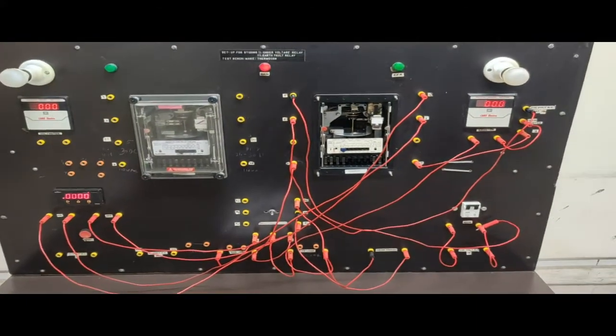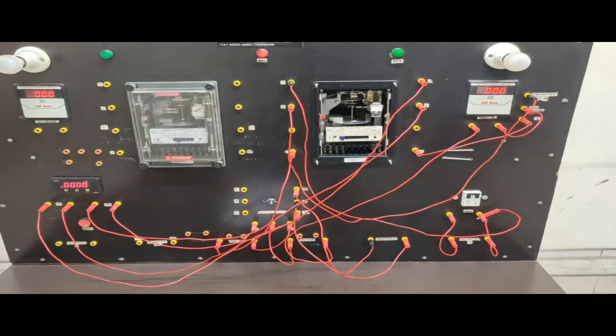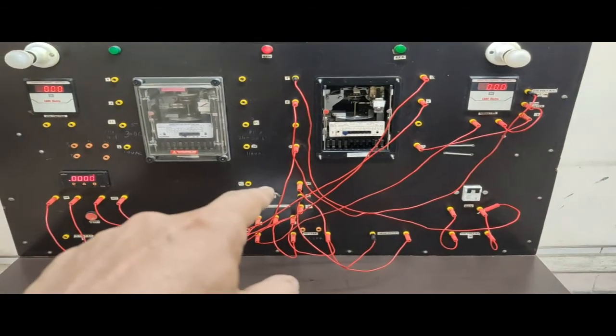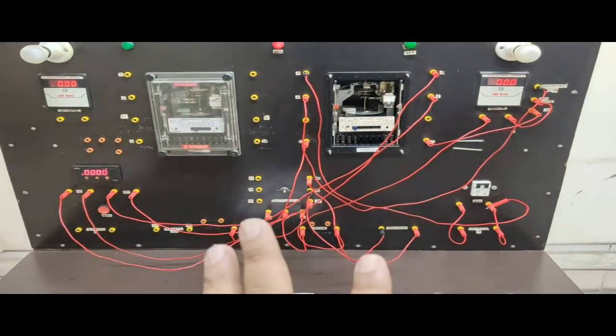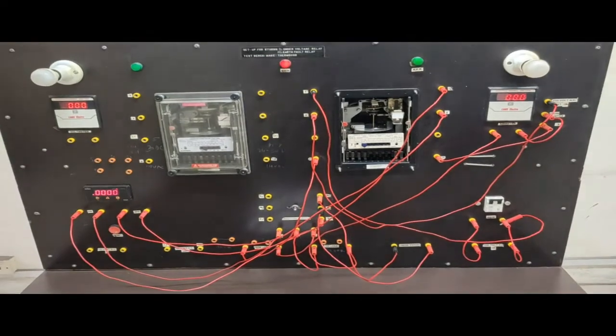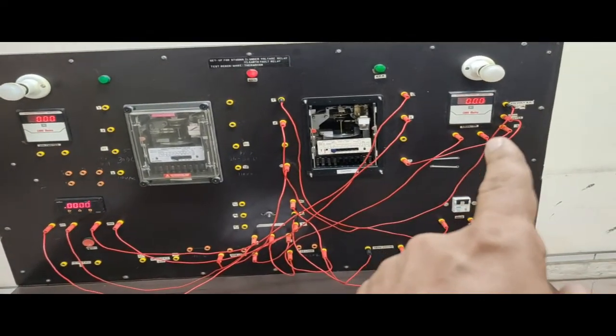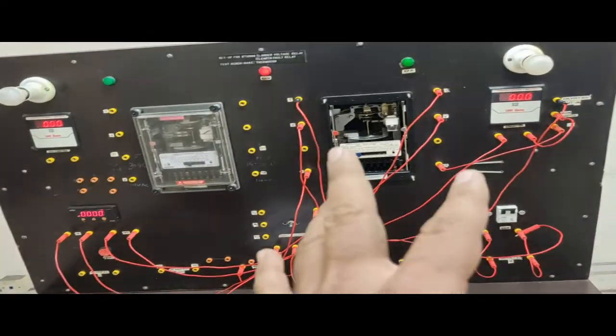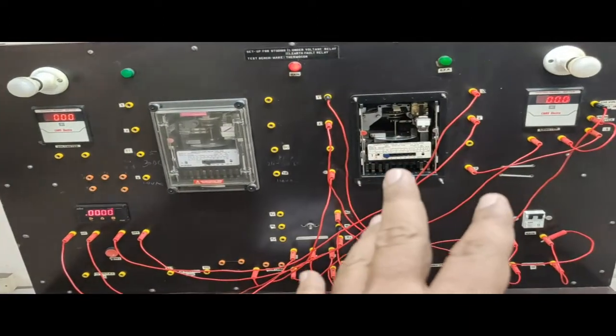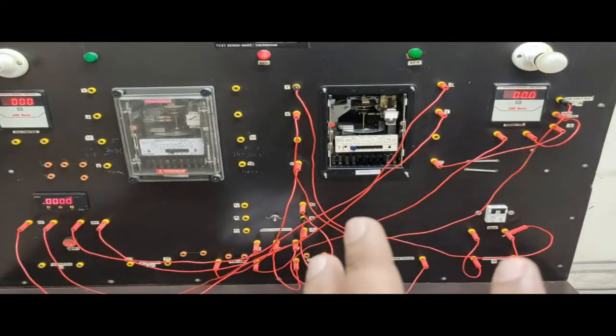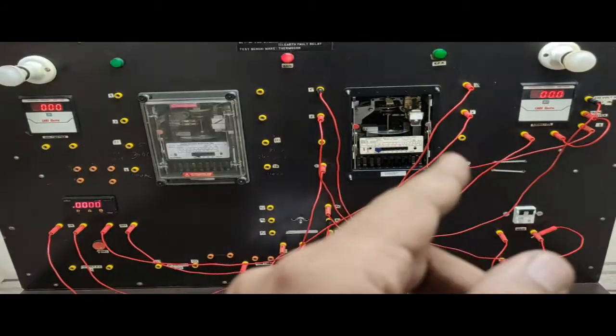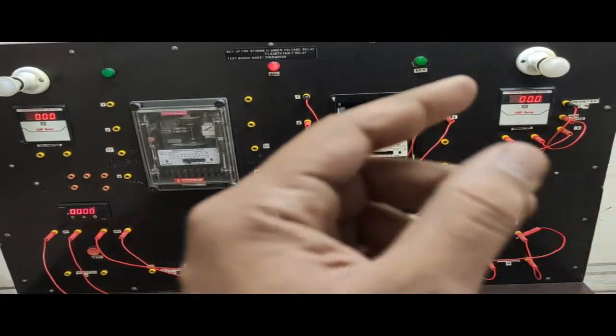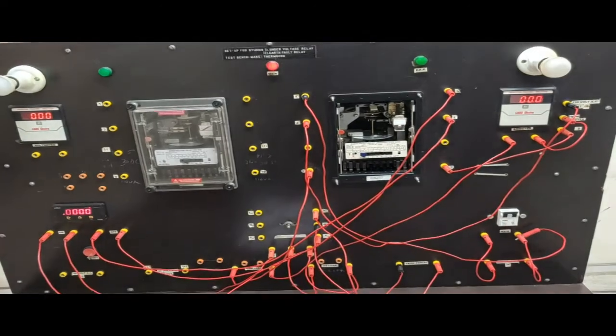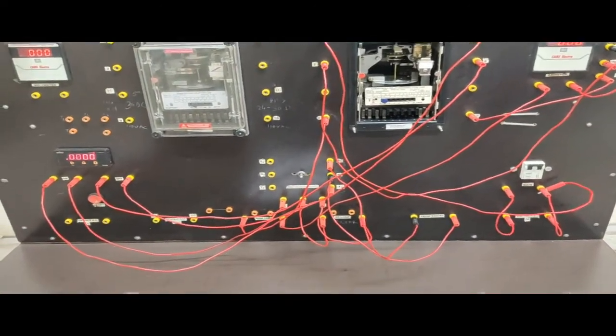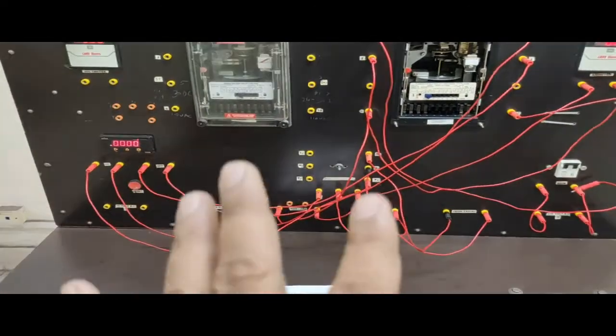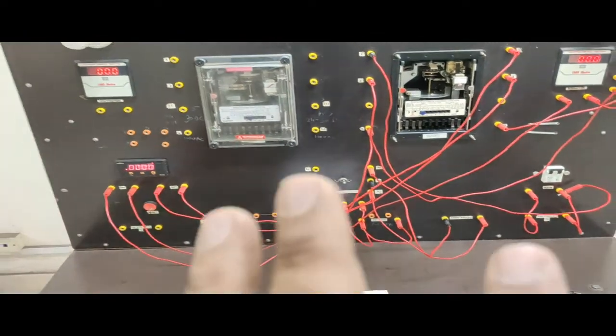Now here the voltage is set, so that means if I switch it on, if I put the selector switch in the downward position, then the required amount of voltage will be applied to the relay and 0.8 ampere current will flow to the relay coil. But according to the tap setting, if only 0.2 ampere current goes through the relay, then the relay will generate the trip signal. The disc will move and ultimately it closes the tripping coil, and the tripping coil will generate the trip signal.